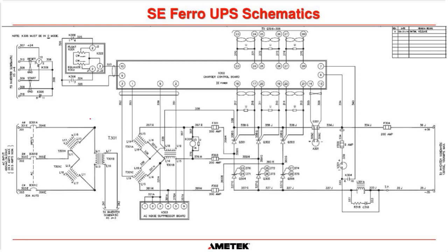and you can see that there is no physical connection between the primary side and the secondary side. So we have an isolation transformer here, and we go from delta to star. So we have our star or Y windings transformer on the secondary. So this transformer is giving us isolation, and in truth, it's a step-down transformer. So phase to phase is going to drop down to around about 120 volts for a 60-cell system. Okay. And then that goes through these 3 fuses into our rectifier bridge.